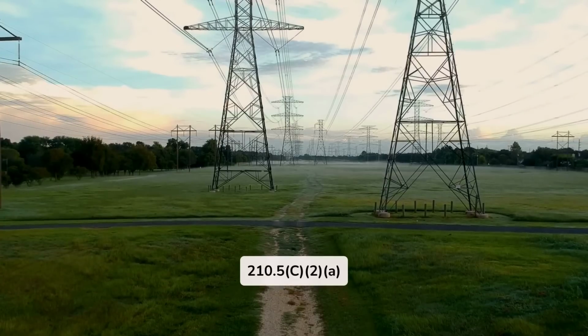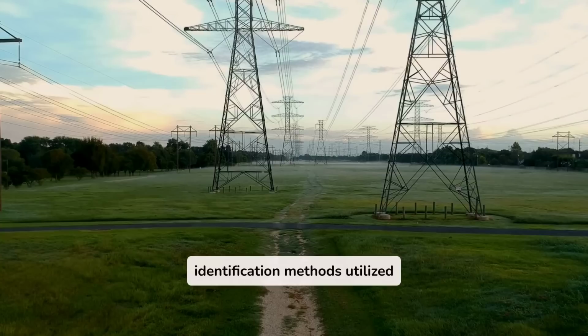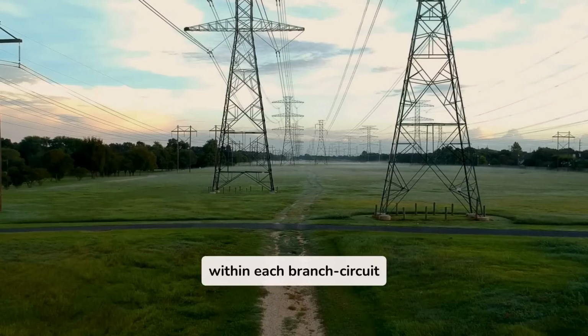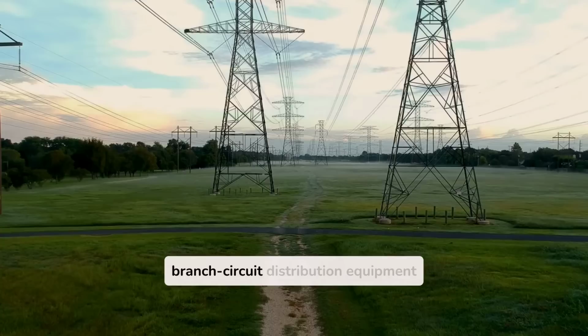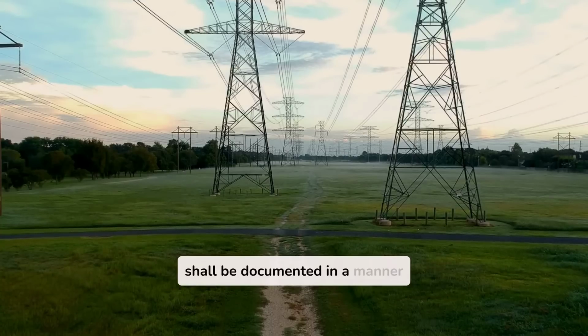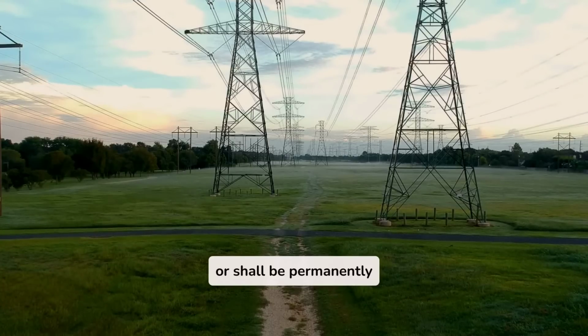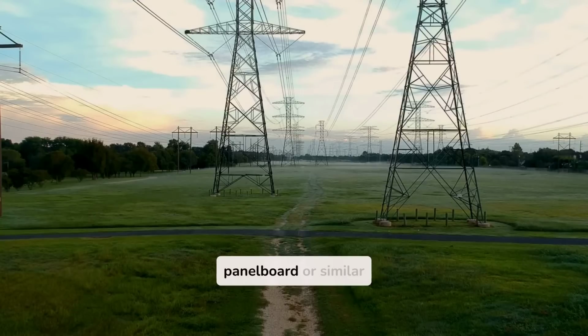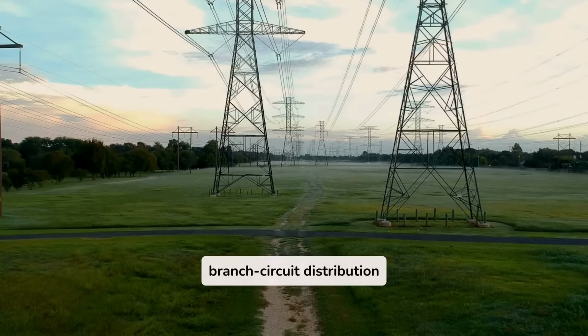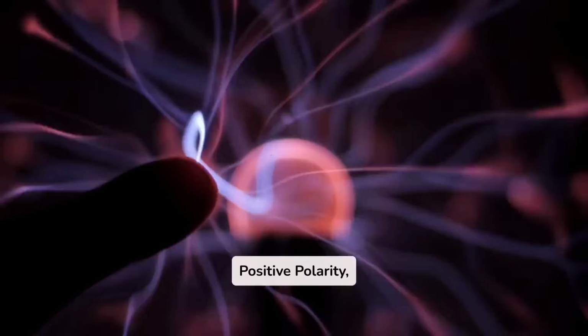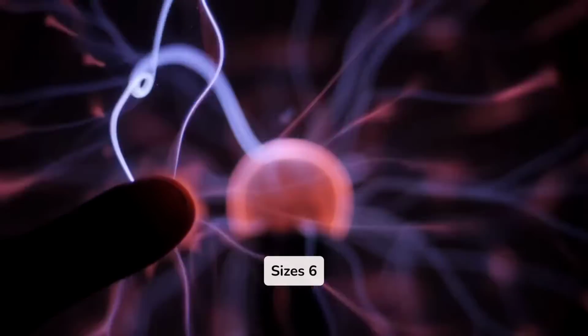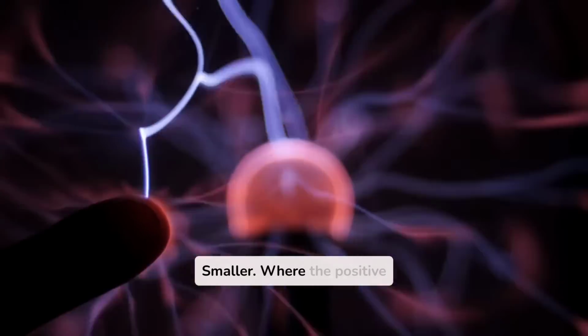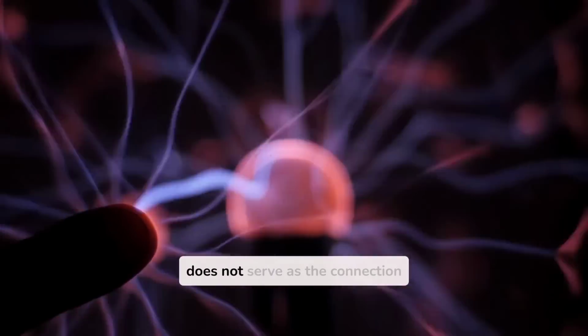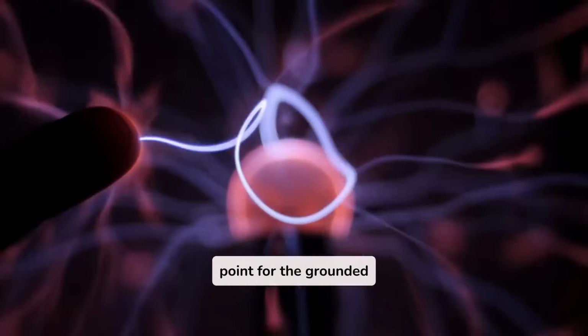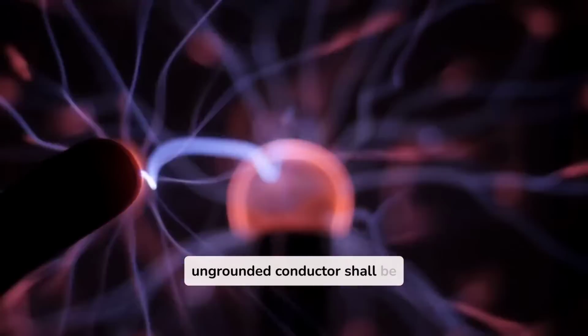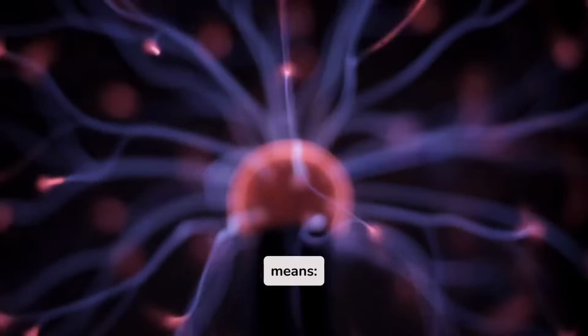The identification methods utilized for conductors originating within each branch circuit panelboard or similar branch circuit distribution equipment shall be documented in a manner that is readily available or shall be permanently posted at each branch circuit panelboard or similar branch circuit distribution equipment. A. Positive polarity, sizes 6 AWG or smaller. Where the positive polarity of a DC system does not serve as the connection point for the grounded conductor, each positive ungrounded conductor shall be identified by one of the following means.